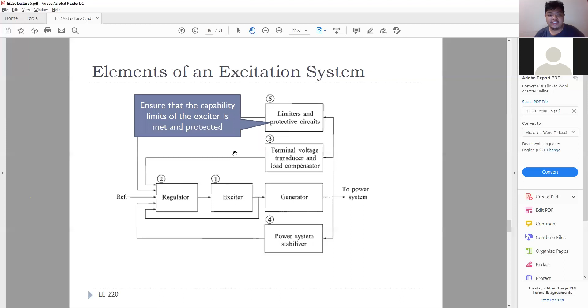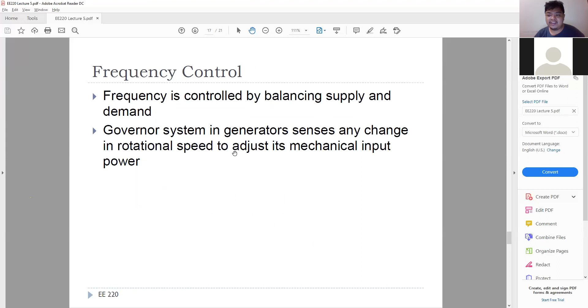Now on the frequency control, frequency is controlled by balancing supply and demand. Now the governor system in generators senses any change in rotational speed to adjust its mechanical input power. There are different modes of operation for generators for frequency control. We have the droop mode, which decreases in speed. Nagde-decrease siya ng speed due to the increase in load.